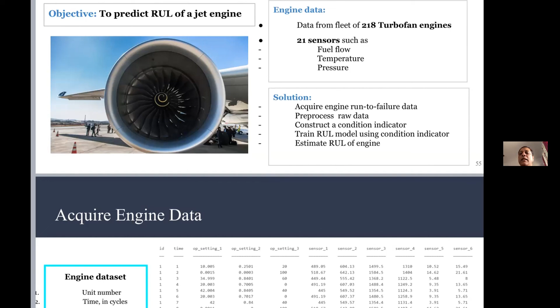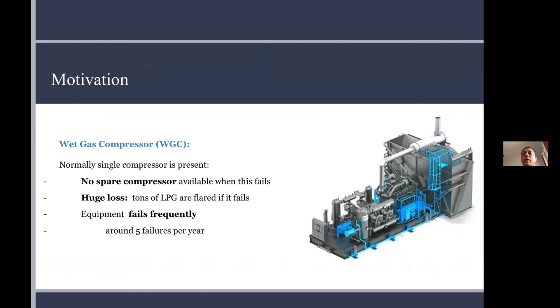Lastly, I'd like to talk briefly about work we did very recently for an elite Indian refinery, on the problem of a wet gas compressor. Normally a single compressor is present with no spare available if it fails, so it's very important that this wet gas compressor should not fail, because if it fails there will be huge loss, with tons of LPG flared. Unfortunately this does happen frequently, around 5 failures per year.